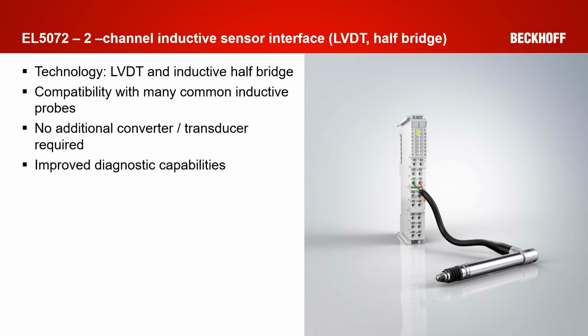In addition, direct integration and evaluation of the signal also offers better diagnosis and simplifies the handling of the data. The terminal can be directly parameterized via EtherCAT and no additional configuration software is required. The signals are read out and forwarded directly via EtherCAT to the controller. We can have a dynamic signal with cycle times in the range of 100 microseconds. The measurement process can be accelerated and thus also save time and costs. Last but not least, various diagnostics are implemented and also allow faster troubleshooting.